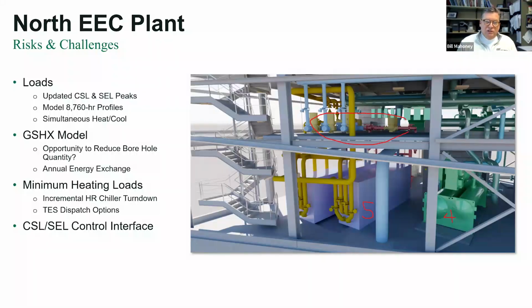It's a bonus here because you're not limited. You're doing a lot of simultaneous heating and cooling. There's full-time winter load here. You've got the thermal storage tank, so you can always dump chilled water into this district system, much more capacity than you would get out of the heat recovery chillers for just those two little buildings. So you couldn't do this campus wide, but it's a great opportunity for the first couple. They'll have great runtime for their simultaneous heating and cooling.